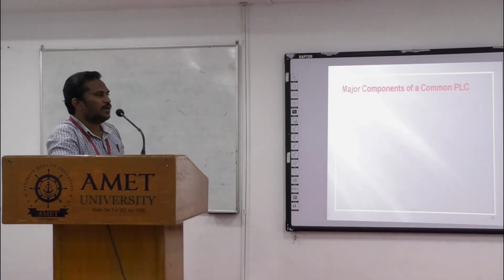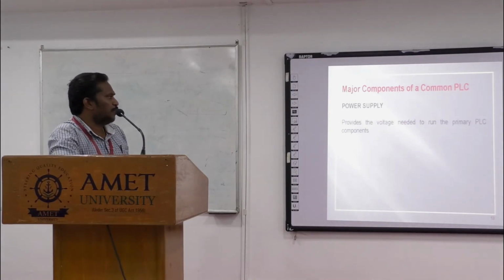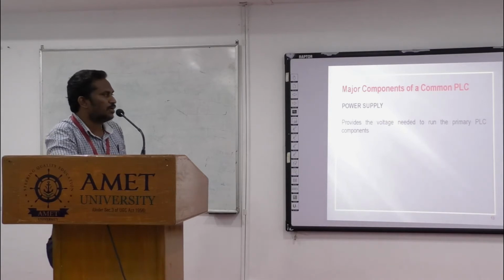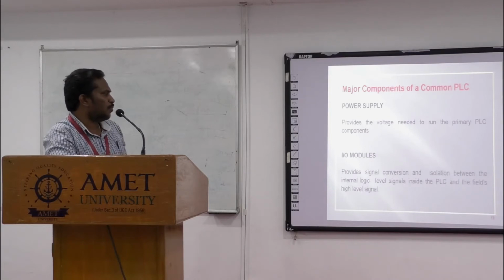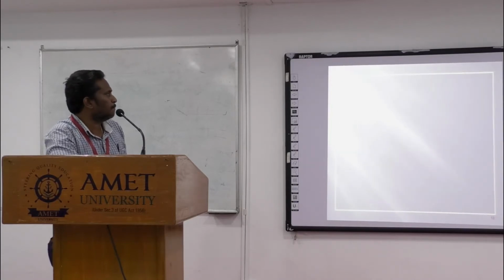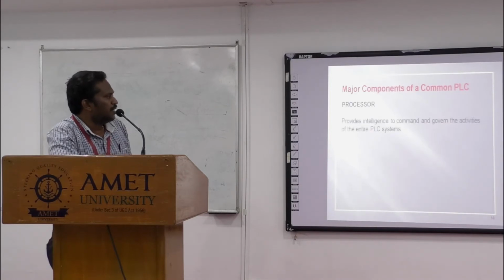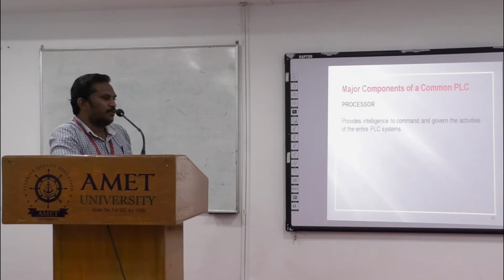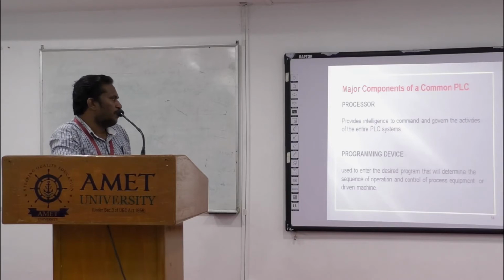Major components of a common PLC. Power supply: the power supply unit provides the voltage needed to run the primary PLC components. I/O modules: the I/O modules provide signal conversion and isolation between the internal logic level signals inside the PLC and the field's high level signals. Processor: it provides the intelligence to command and govern the activities of the entire PLC system. Programming device: it is used to enter the desired program that will determine the sequence of operation and control of the process, equipment or driven machine. The programming device types are a handheld unit with LED or LCD display, a desktop type with CRT display, or a compatible computer terminal, or we can use a laptop also as a programming device.